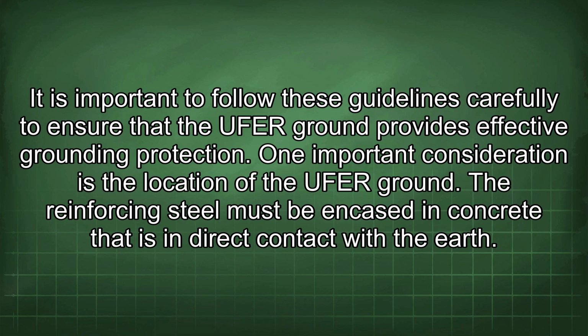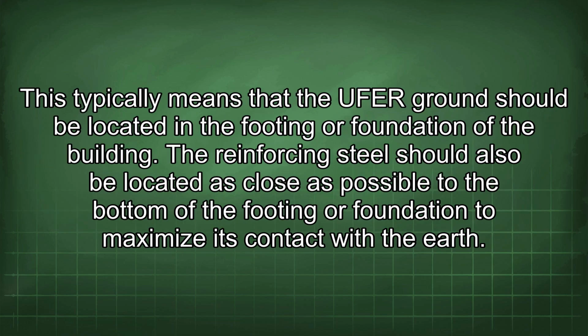One important consideration is the location of the UFER ground. The reinforcing steel must be encased in concrete that is in direct contact with the earth. This typically means that the UFER ground should be located in the footing or foundation of the building. The reinforcing steel should also be located as close as possible to the bottom of the footing or foundation to maximize its contact with the earth.